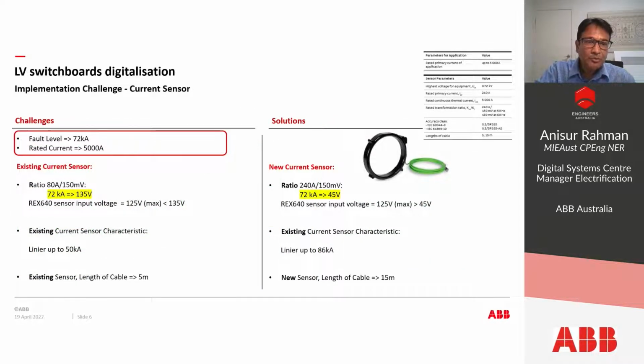The LV switchboard fault level is more than 72 kA, and the rated current is 5000 ampere. So the ratio of all the existing sensors was 80:150 millivolt. And if you convert that for 72 kA, the output voltage becomes 135, which is more than the threshold voltage of the REX 640 or any relays.